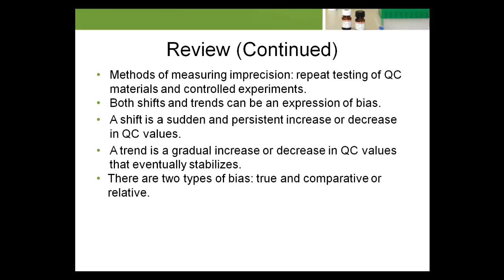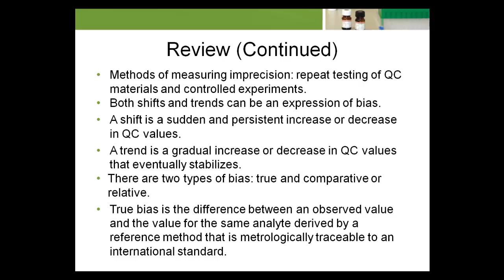There are two types of bias: true and comparative or relative. True bias is the difference between an observed value and the value for the same analyte derived by a reference method that's metrologically traceable to an international standard. Comparative or relative bias is the difference between an observed value and the calculated value of a consensus group for the same analyte. The peer group is the ideal and preferred group for statistical comparisons.